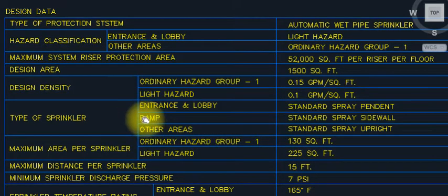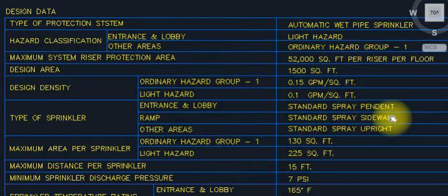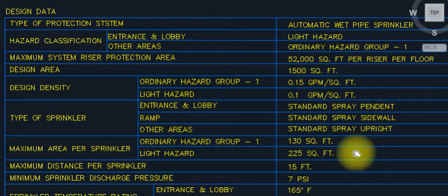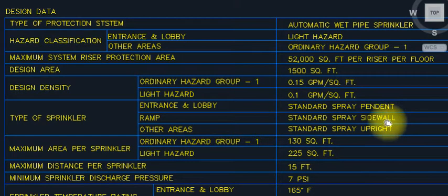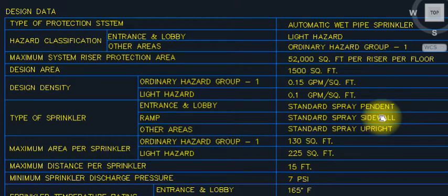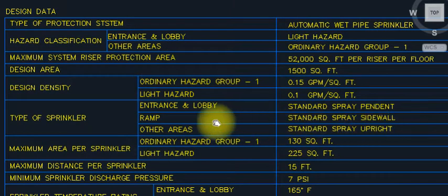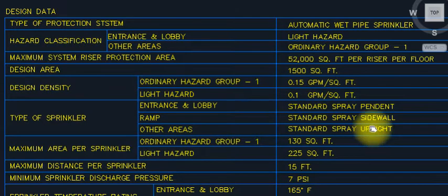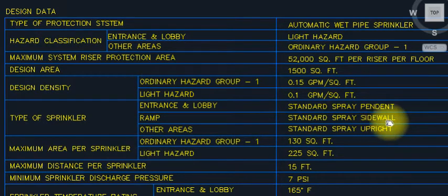For the ramp area, always use sidewall sprinklers — keep this in mind. We do not use pendant type or upright in the ramp area. We always use sidewall because a car could be hit if you provide a pendant type overhead. The sprinkler comes from the wall, so we use sidewall in the ramp area.